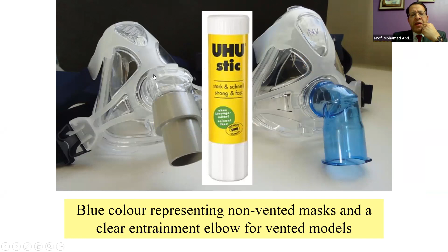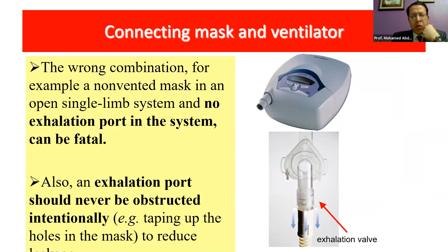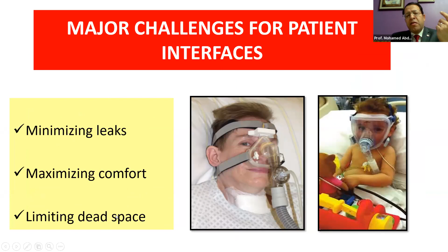So if you look to the elbow, if it is blue, this is a non-vented mask, and if the elbow is clear, this is a vented mask, and it is wrong to close this vented mask because you are going to make the patient suffocate. Major challenges for patient interfaces are to minimize the leak, maximize the comfort, and limit the dead space, and this should be achieved by customizing the mask.